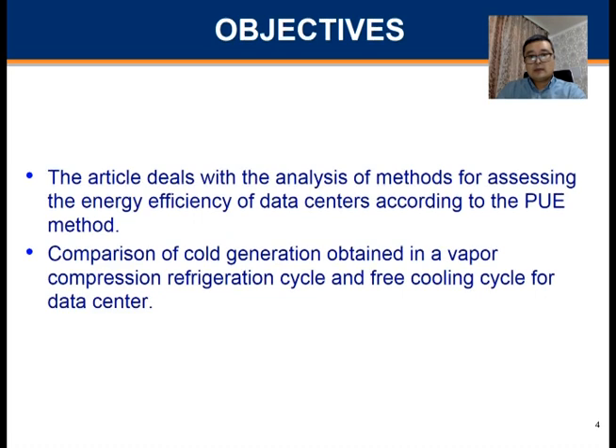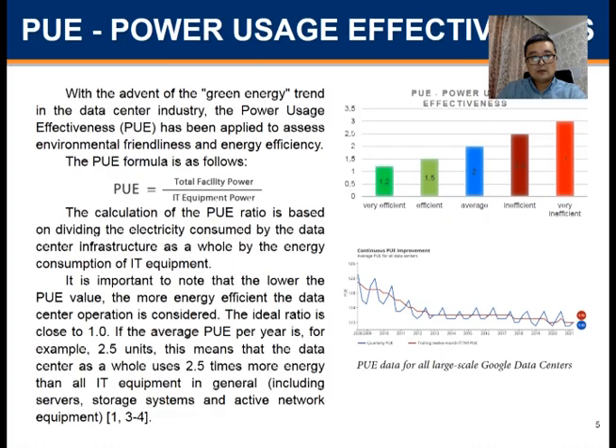The article deals with the analysis of methods of assessing the energy efficiency of data centers according to the PUE method, comparison of cold generation obtained in a vapor compression refrigeration cycle, and the free cooling cycle for a data center. With the advent of the green energy trend in the data center industry, power usage effectiveness has been applied to assess environmental friendliness, the energy efficiency. The PUE formula is as follows: total facility power divided by IT equipment power.